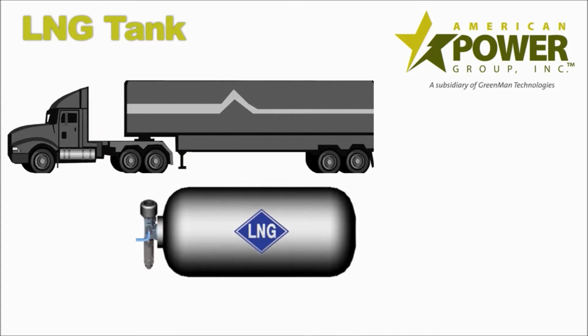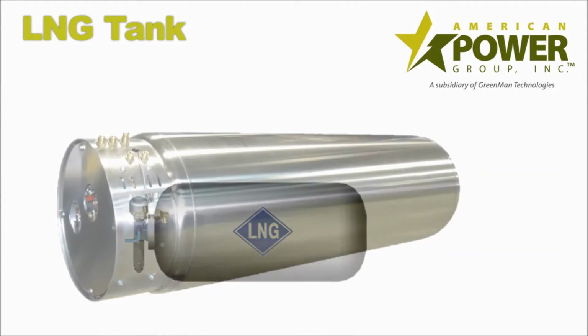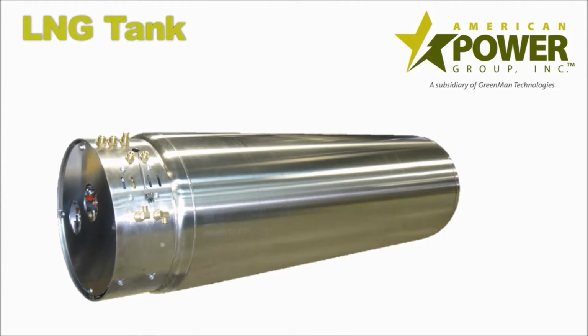Because LNG is stored as a cryogenic liquid at roughly minus 150 degrees Celsius, the LNG tank requires insulation. It uses a double-walled stainless steel construction. The void between the inner and outer layers of the tank is a vacuum. The vacuum insulation is so effective that it will keep the LNG cold for over a week, regardless of the ambient temperature.